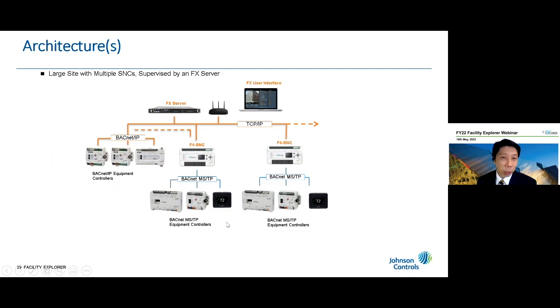Then extend further for a large site, so you can expand the SNC, multiple SNCs, to form a bigger network through the MSTP trunk and the IP trunk together, supervised by an FX server. All will talk in BACnet IP in the integration between server and SNC.